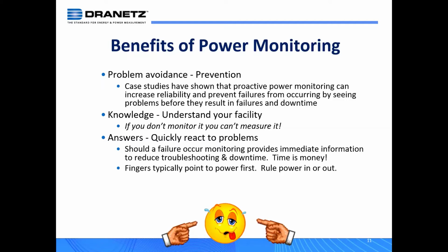And fixed monitoring is extremely important. So something goes down, you need to know, A, was it a power problem? Because sometimes it isn't. It could be an IT issue, a server issue, or something else unrelated to power, just an equipment failure. And if it is a power problem, it gives you that information to understand what happened and possibly where it originated. So this is the key stuff, lets you get back up and running much quicker.